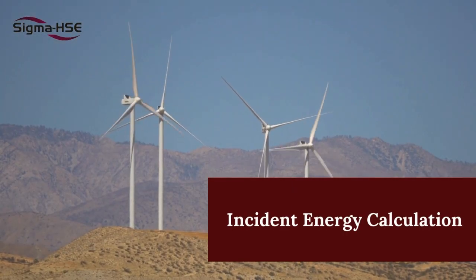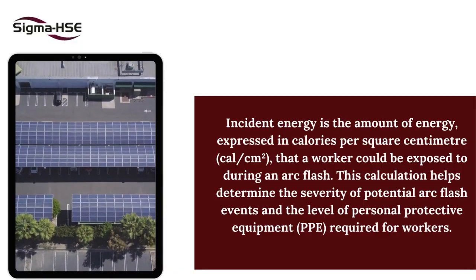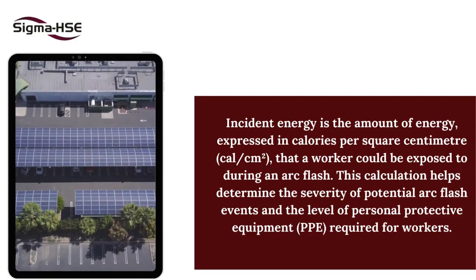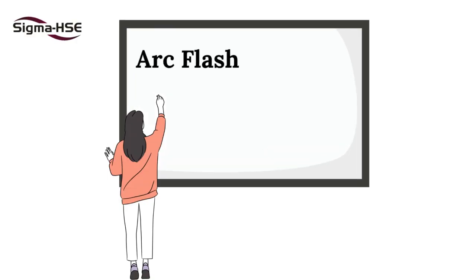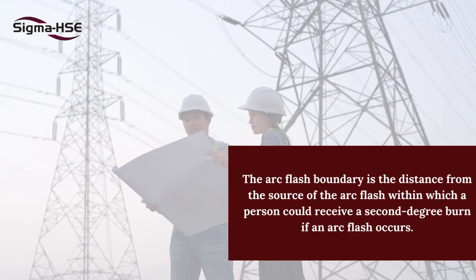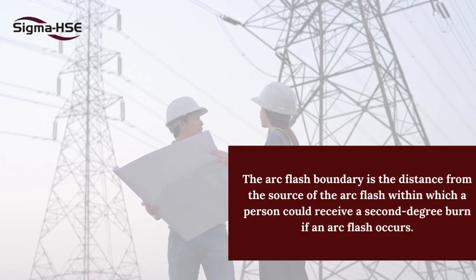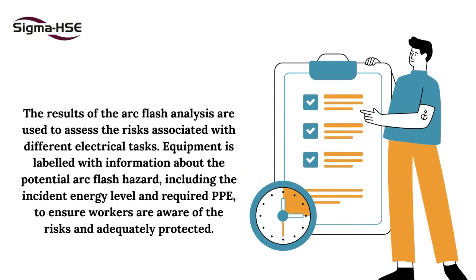Incident Energy Calculation: Incident energy is the amount of energy, expressed in calories per square centimeter, that a worker could be exposed to during an arc flash. Arc Flash Boundary Determination: The arc flash boundary is the distance from the source of the arc flash within which a person could receive a second-degree burn if an arc flash occurs. Risk Assessment and Labeling: The results of the arc flash analysis are used to assess the risks associated with different electrical tasks.